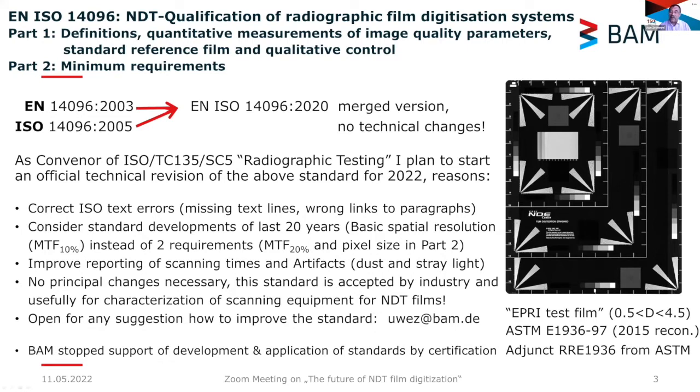For scanner characterization, we have such a test film here, which we developed together with the EPRI. This is the Electric Power Research Institute in the nuclear field in North Carolina in the US. This went into an ASTM standard in 1997, which was reconfirmed in 2015.